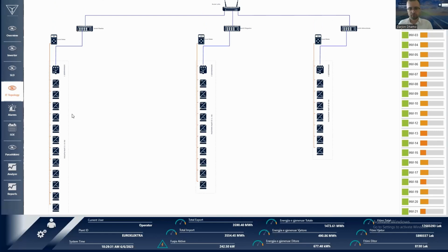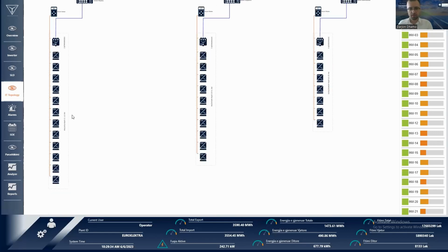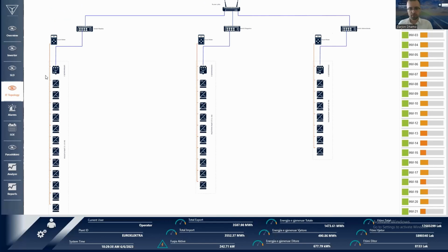So for Lufra Plastic, there are 12 inverters which are connected with the data manager, which is the data logger. The inverters communicate with the data manager through SolarNet protocol. And also the smart meters communicate with the data manager through Modbus RTU protocol through RS485 interface.